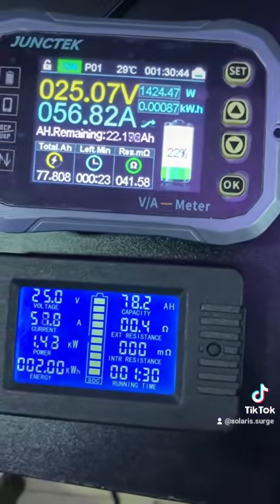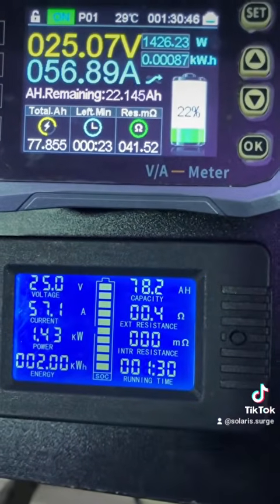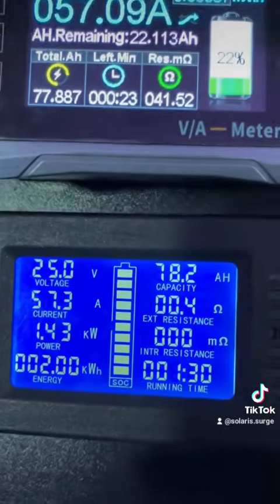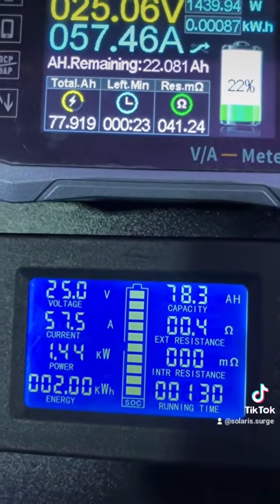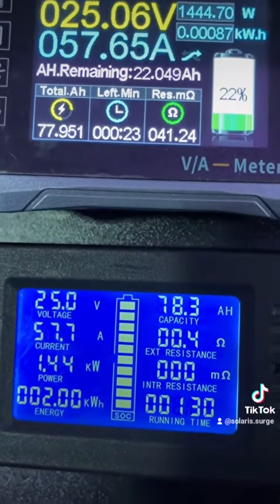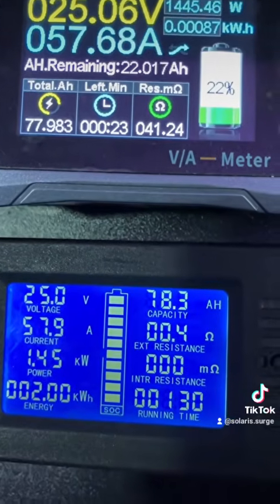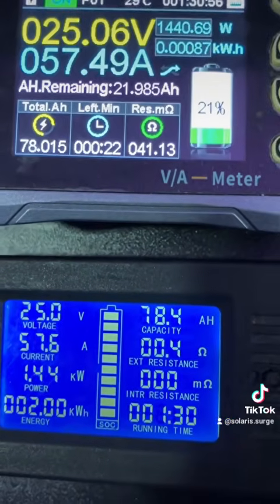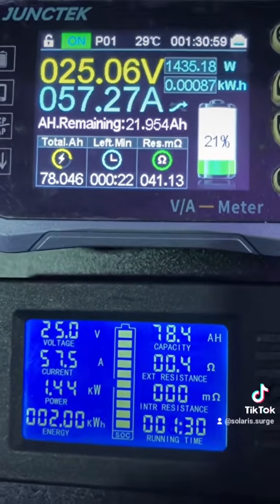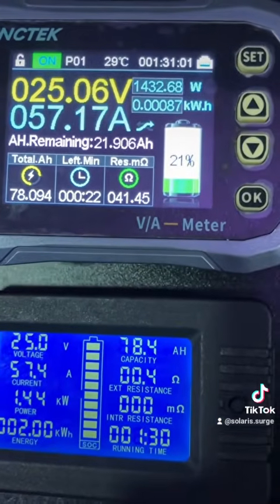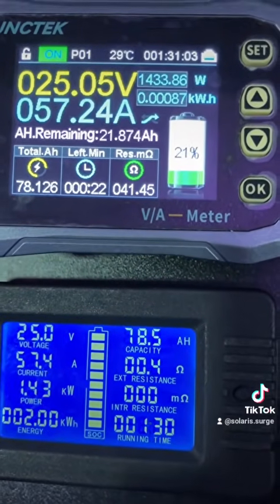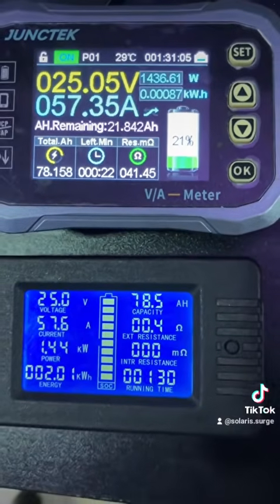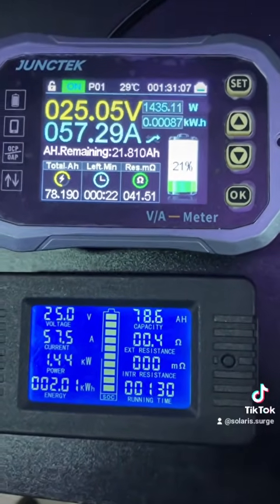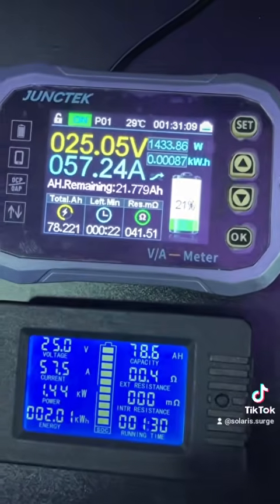1 hour 30 minutes into the test, we have done 2 kilowatt hours, still drawing 1.45 kilowatts at 57.6 amps. Our battery voltage is at 25 volts. We have used 78.5 amp hours after 1 hour 30 minutes of running an inverter AC at full power.